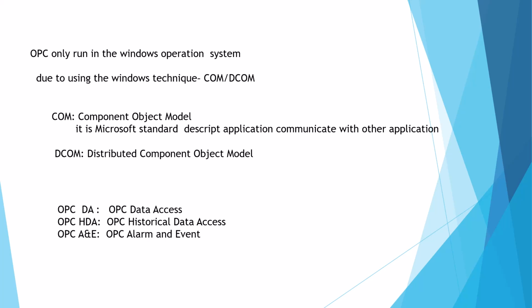OPC can run in the Windows operating system because it uses the Windows techniques COM and DCOM. COM means Component Object Model. It's a Microsoft standard describing how applications communicate with each other. DCOM means Distributed Component Object Model. So with OPC, we often use three types: OPC-DA, OPC-HDA, OPC-A and E. OPC-DA is OPC Data Access. OPC-HDA means OPC Historical Data Access. OPC-A and E is OPC Alarm and Event.